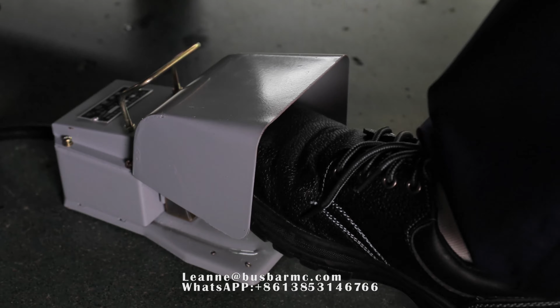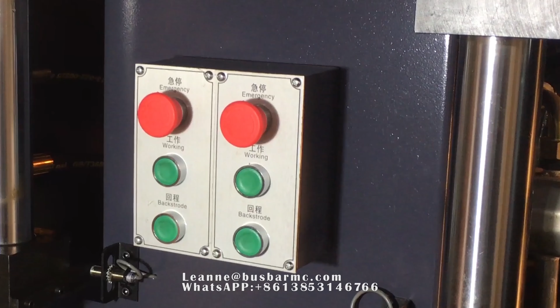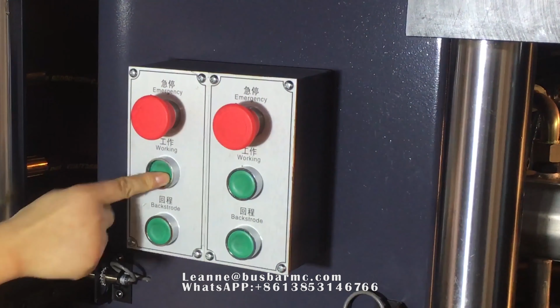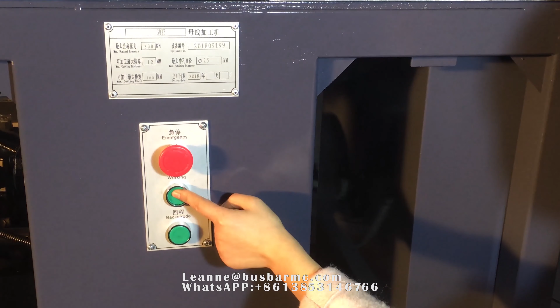Check whether the power wires are connected correctly or not. Lightly step on the foot switch of the cutting station, or press the working button of the cutting station. If the cutting station runs normally up and down, the connection of the power wire is normal. If the machine motor is rotating, but the cutting station cannot run normally up and down, please first cut off the total power supply, then open the electrical cabinet. Switch the order of any 2 phases of L1, L2, L3. Energize again, and the machine can run normally.